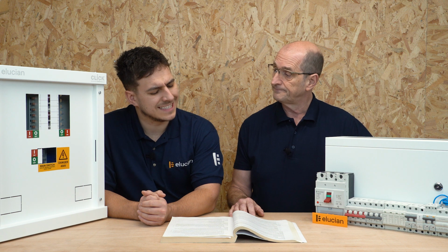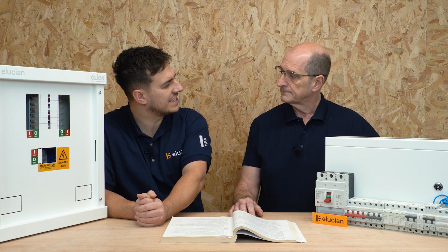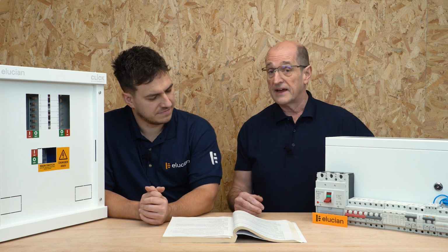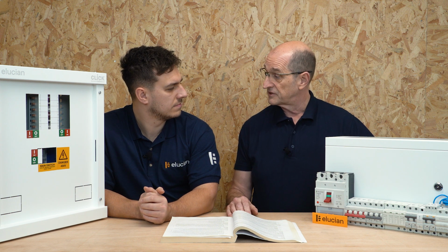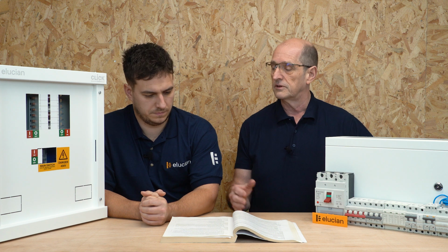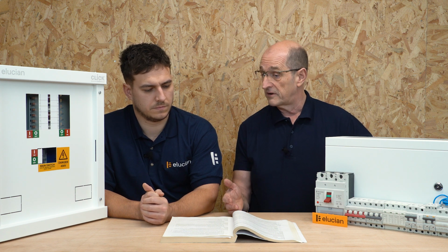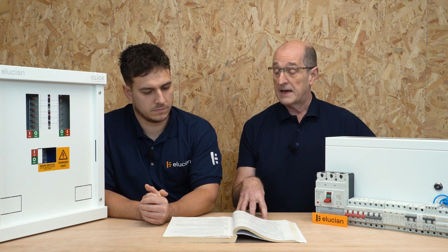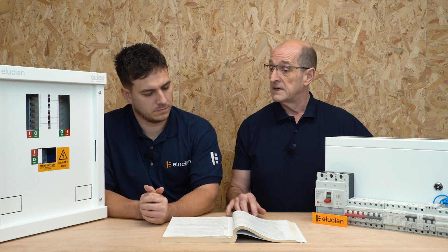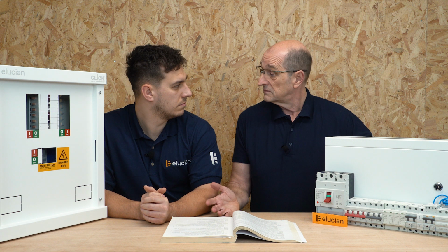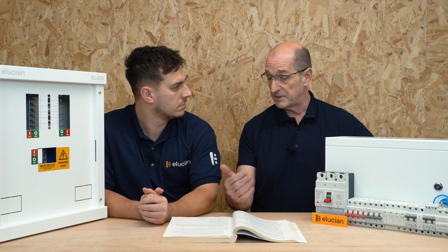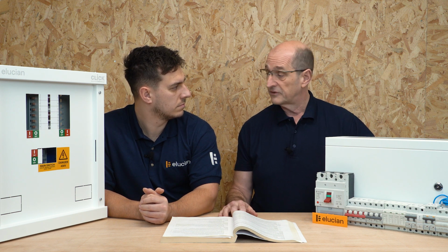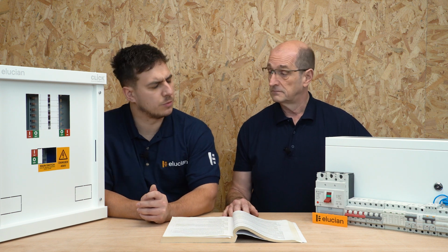You've mentioned DC there, though. We generally deal with AC. We do, but the things we connect up create a DC connection onto our system, and so it sticks a certain level of DC current onto the protective conductor. It might be via a functional earth, it might be for all sorts of other reasons, but we do create that. And we also connect up to DC components. A battery is a DC component, whether it be in a car or from a solar PV system, there is DC. Okay. So how do we know which one we need to select then?